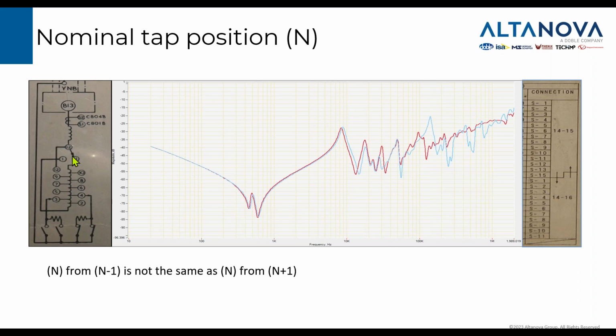Then position of this changeover selector is also important, and this can be mistaken when you measure tap change transformer on nominal tap position. Nominal, I mean actually the middle tap position when changeover selector switches from one position to another. It switches after nominal tap position. So when it goes from bottom tap position, from lowest tap to highest tap, it will switch after that tap, and vice versa when it's going from top tap to the bottom tap, again after that tap, but this is when you test the tap transformer in nominal tap position.